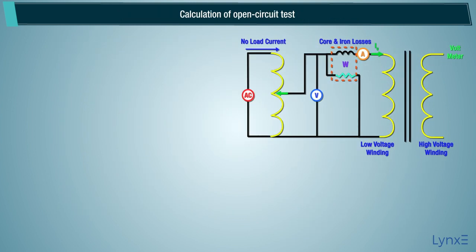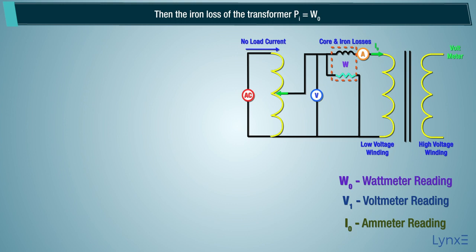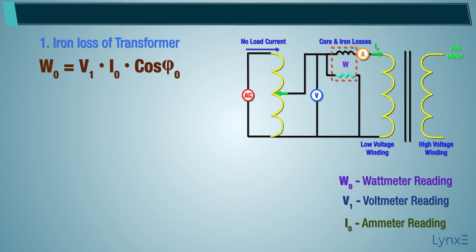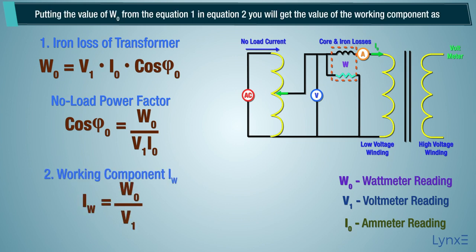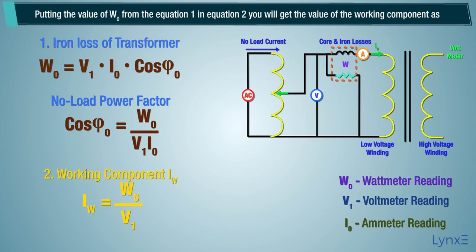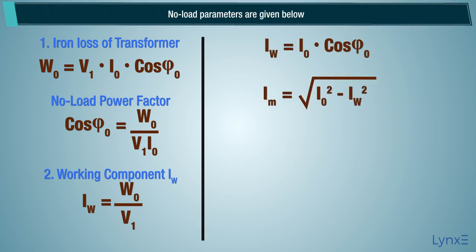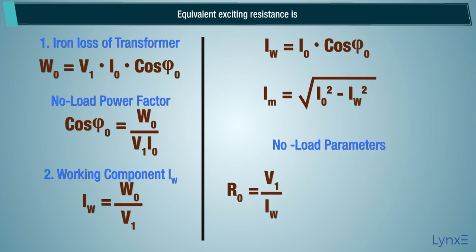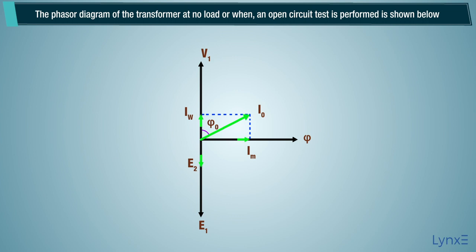Calculation of open circuit test: Let W0 be the wattmeter reading, V1 be the voltmeter reading, and I0 be the ammeter reading. Then the iron loss of the transformer PI equals W0. The no-load power factor is determined, and the working component IW is found by putting the value of W0 from equation 1 into equation 2. The magnetizing component is also calculated. The no-load parameters — equivalent exciting resistance and equivalent exciting reactance — are given by the derived formulas. The phasor diagram of the transformer at no-load or when an open circuit test is performed is shown below. The iron losses measured by the open circuit test are used for calculating the efficiency of the transformer.